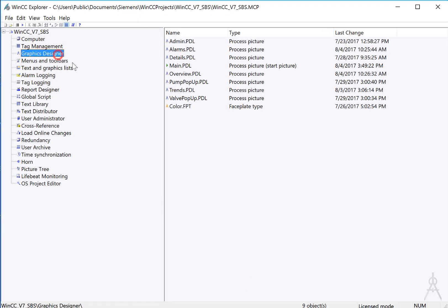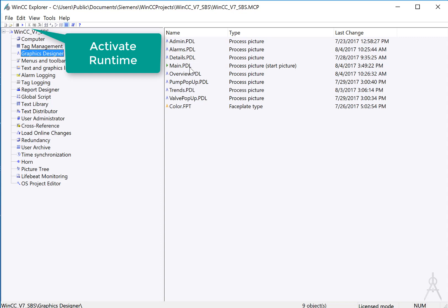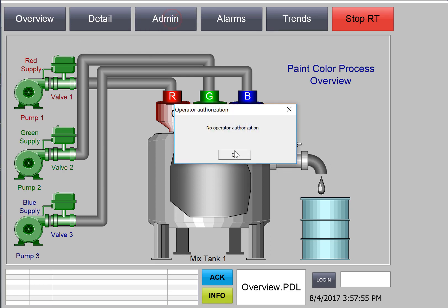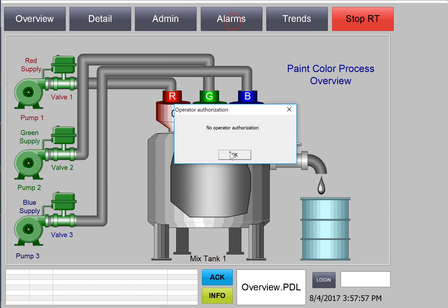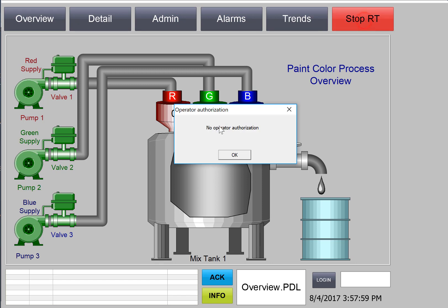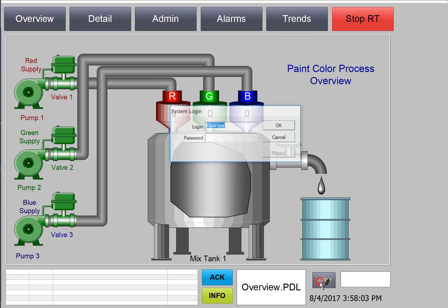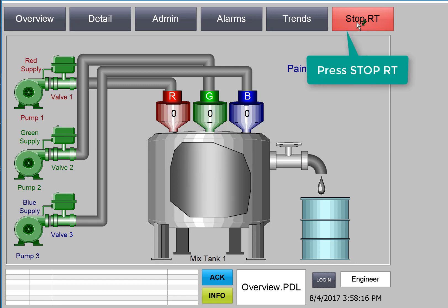Then highlight Graphics Designer and make sure that Main is your default start picture. This is pretty important because it has the controls to allow you to log on. Then we're just going to go to runtime. So you can see the runtime window is full screen, and I am locked out of doing things, especially like stopping RT. And I should be able to click my login screen. If you did forget to do this, you can use Control-L. I can log on as my engineer, and then I can use Stop RT to deactivate the project.